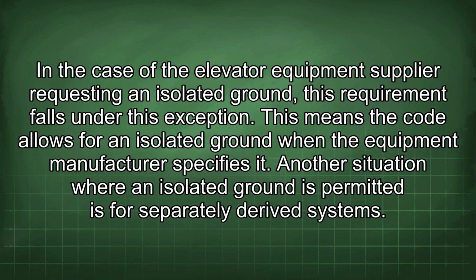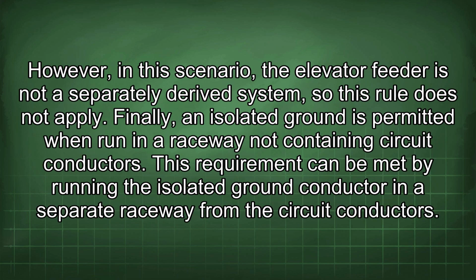In the case of the elevator equipment supplier requesting an isolated ground, this requirement falls under this exception. This means the code allows for an isolated ground when the equipment manufacturer specifies it. Another situation where an isolated ground is permitted is for separately derived systems. However, in this scenario, the elevator feeder is not a separately derived system, so this rule does not apply. Finally, an isolated ground is permitted when run in a raceway not containing circuit conductors. This requirement can be met by running the isolated ground conductor in a separate raceway from the circuit conductors.